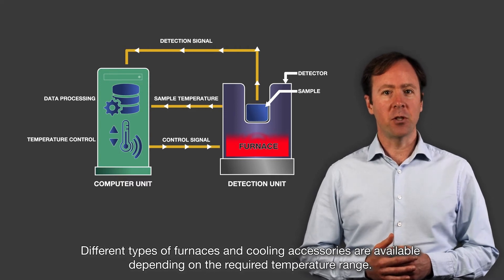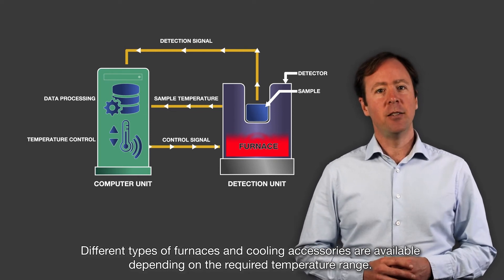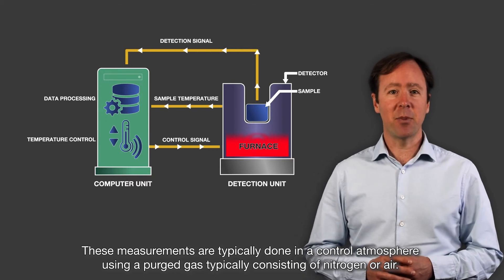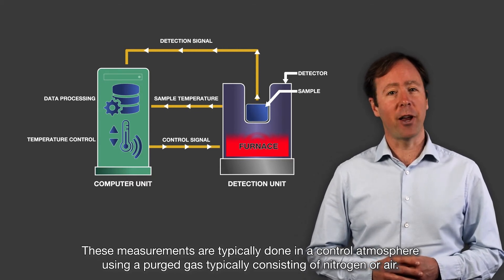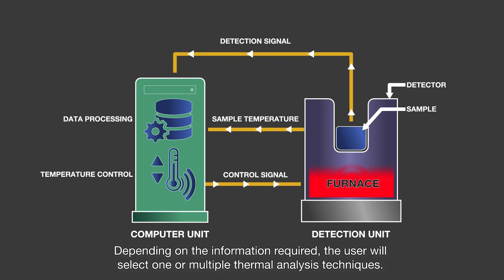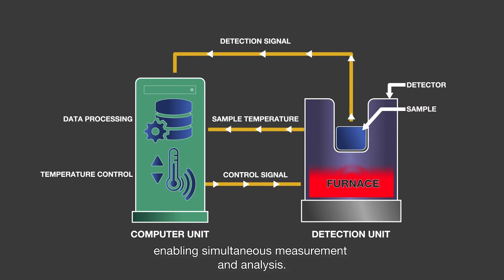Different types of furnaces and cooling accessories are available depending on the required temperature range. These measurements are typically done in a controlled atmosphere using purge gas, typically consisting of nitrogen or air. The temperature control, data recording and analysis are all computer controlled. Depending on the information required, the user will select one or multiple thermal analysis techniques. The computer can be connected to several instruments enabling simultaneous measuring and analysis.